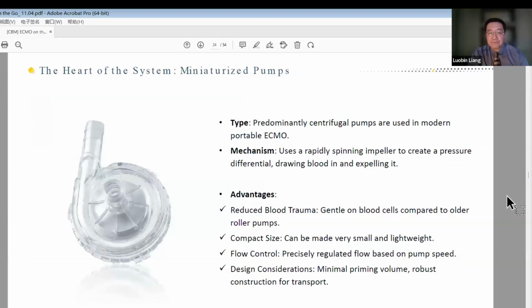Yeah, like the pump system, we want to make the pump smaller. We want to make it using a less priming volume, and then so they can have a better biocompatibility to reduce blood trauma, to be gentle to the blood compared to the older, bigger centrifugal pump or old time roller pump. And then we need a compact size, making it smaller and lightweight to reduce the whole weight of the system. We need a flow control, precisely regulated flow based on the pump speed. And then the design consideration is to minimize the priming volume, also has a robust construction for transport.